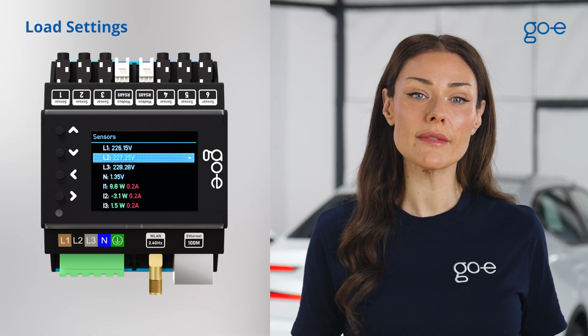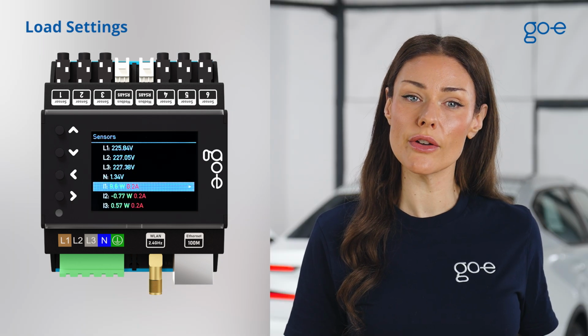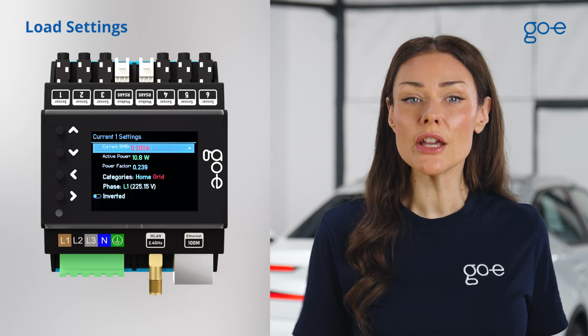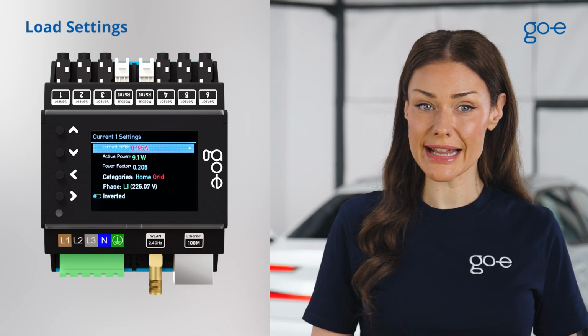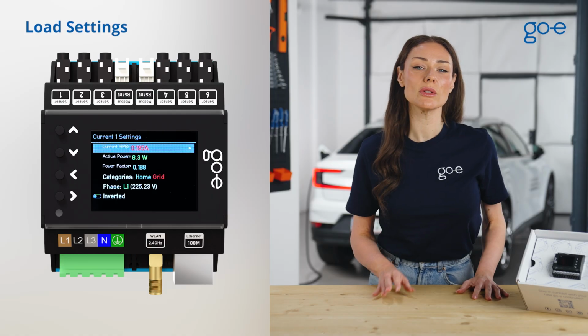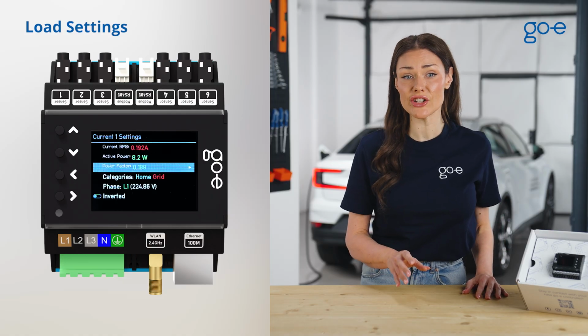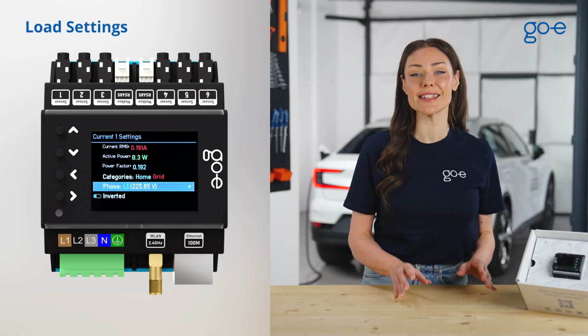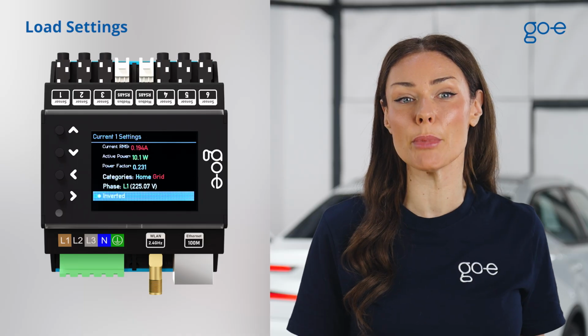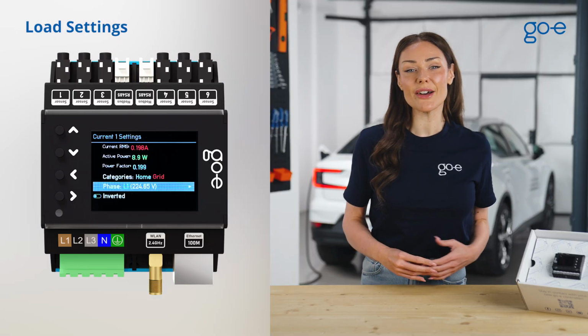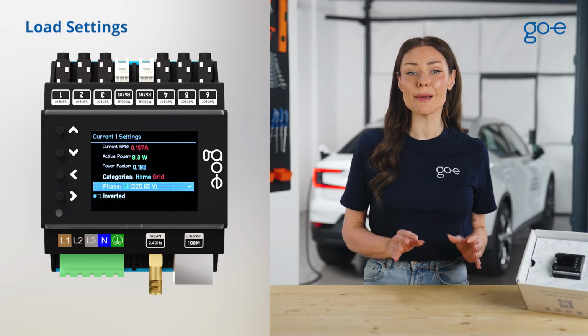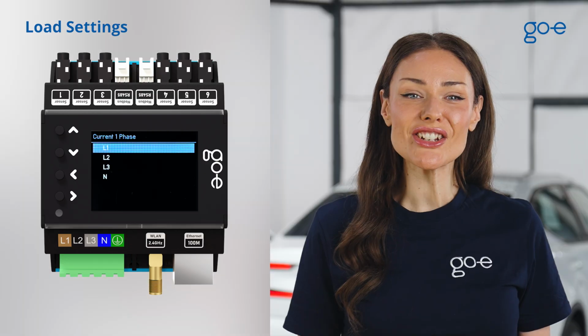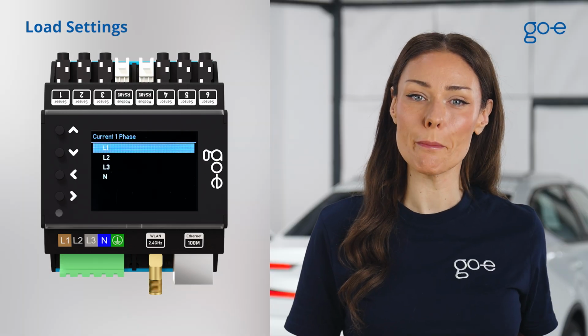If you select one of the 6 current sensors from the overview, for example I1, you'll access the corresponding load settings. If it turns out that you've installed a current transformer in the wrong direction, you can invert the load using the slider option, which reverses its polarity. For accurate power calculation, the phase reference must be set correctly. Imagine the sensor measures 2 amps on your mains connection. Without a voltage reference, the controller can't know whether you're feeding power into the grid or drawing from it.